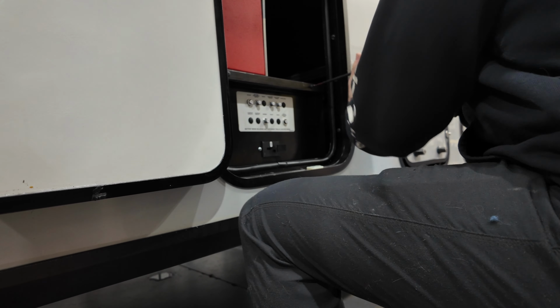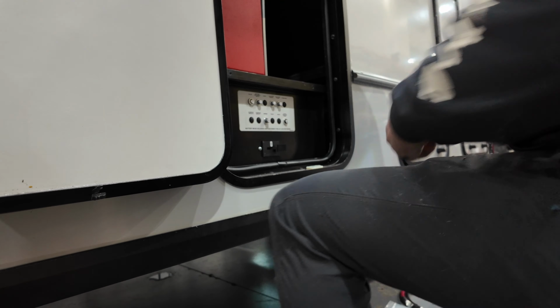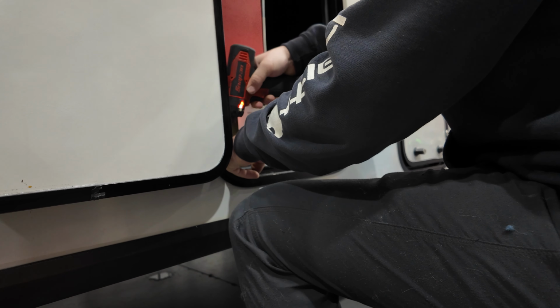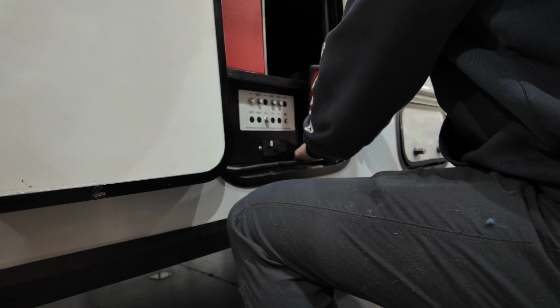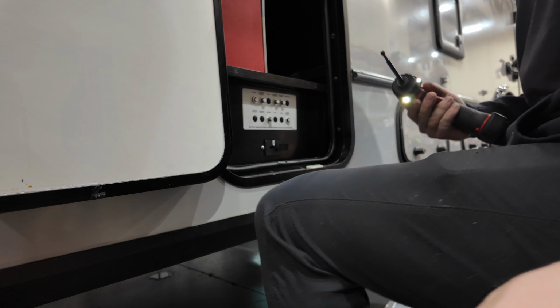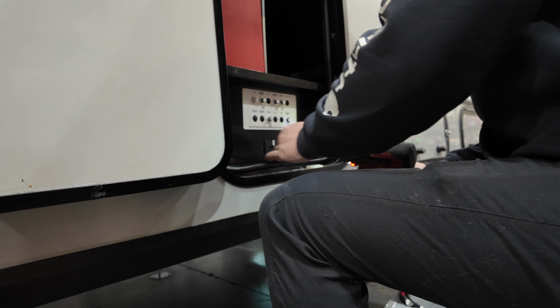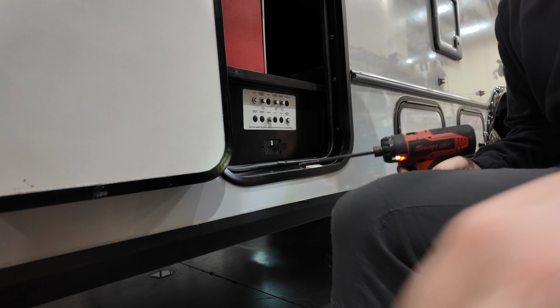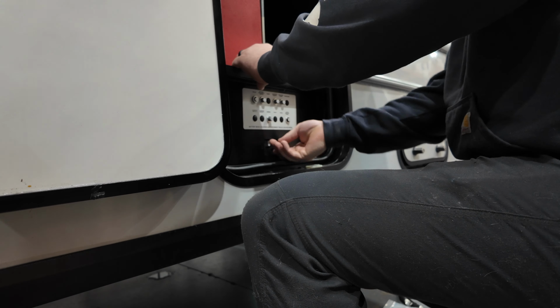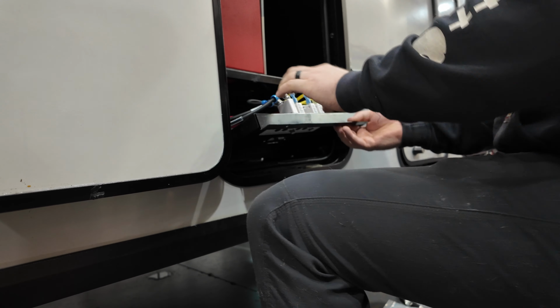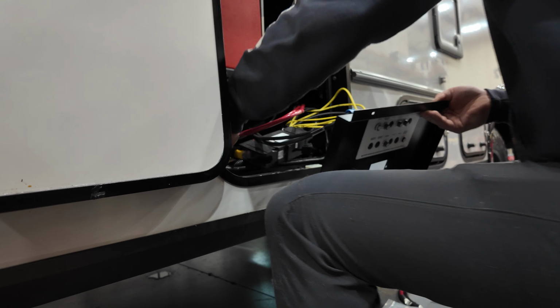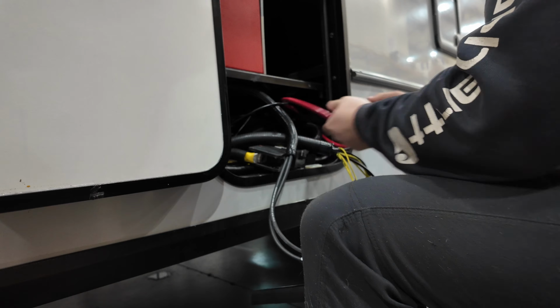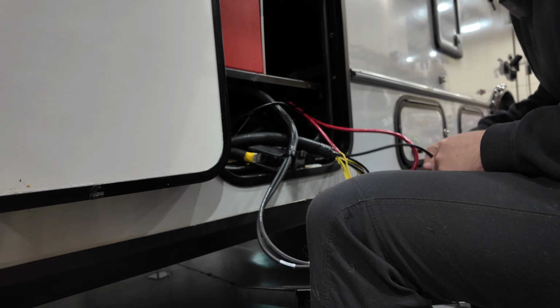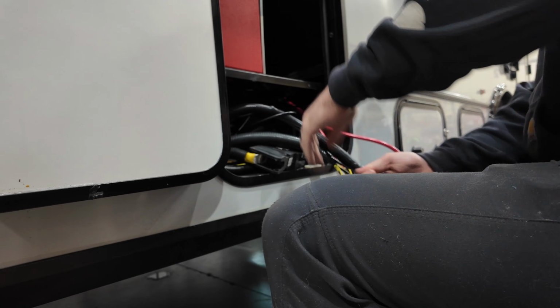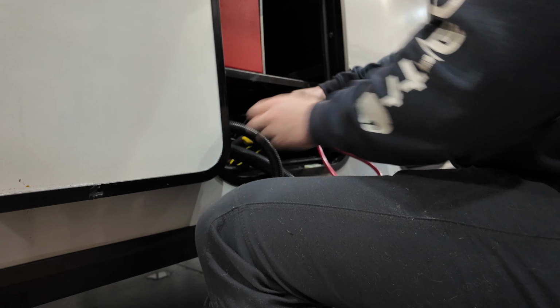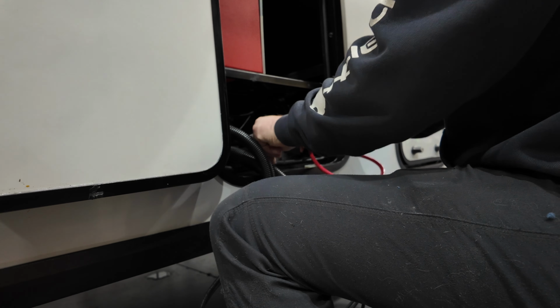So we're going to begin deconstruction of the compartment. There's 2 screws on the top and 3 on the bottom. Once those are out, the faceplate is moving freely. We'll take the 2 screws out of the 250 amp breaker and push it back, then gently pull the faceplate out of the compartment and lay it down. The wires are fine to support that faceplate and keep it out of the way while working. I recommend getting a 2x4 or something non-conductive to set the 250 amp breaker on inside the compartment, just to keep it supported and out of the way.